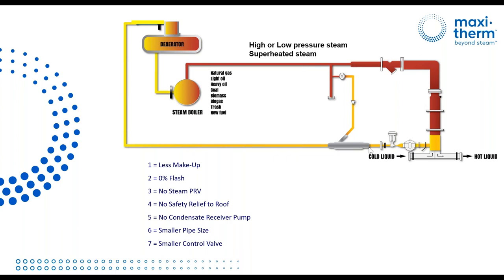So 20% of our projects, especially our retrofits, are low pressure steam. Let's say we're coming in at 15 PSI here. After the control valve, typically you want to lift. Let's say we're lifting 10 feet high. Every 27 inches gives you 1 pound back pressure, so you're going to have about 5 PSI back pressure. You're coming in at 15, you don't need a condensate pump. When you go the conventional way with a horizontal shell and tube, typically at 70% of the load and lower, you're operating at 0 PSI. So if you're lifting 2 feet after the trap, you'll need a pump.